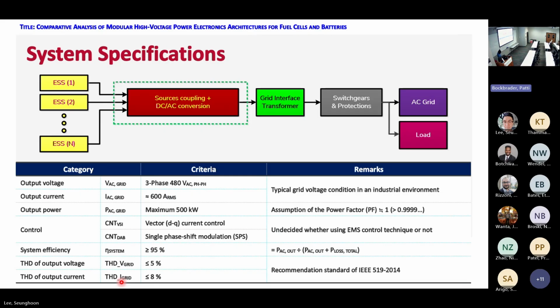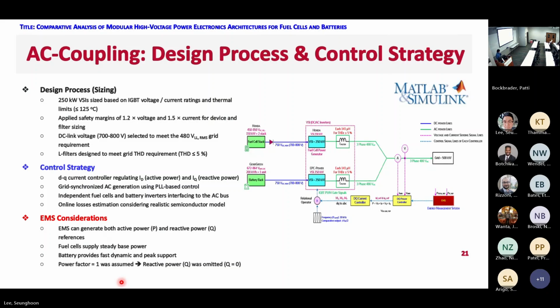System efficiency is more than 95%, and the output voltage and current THD values are less than 5 and 8%. It is used for the IEEE 519 standard. So for this design, the inverters are configured in 250 kilowatt building blocks with a safety margin of 1.2 times voltage and 1.5 times current applied to meet device and thermal limits.